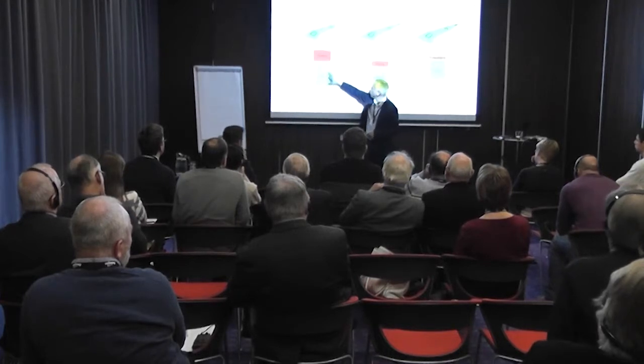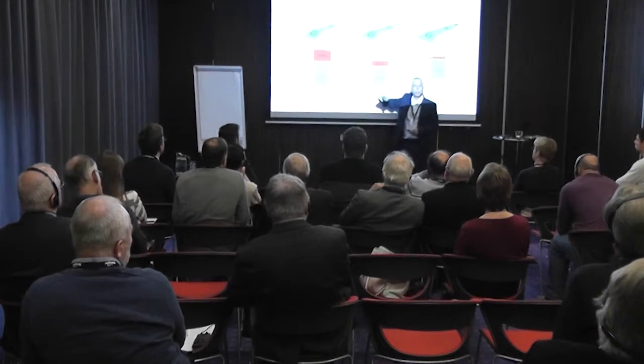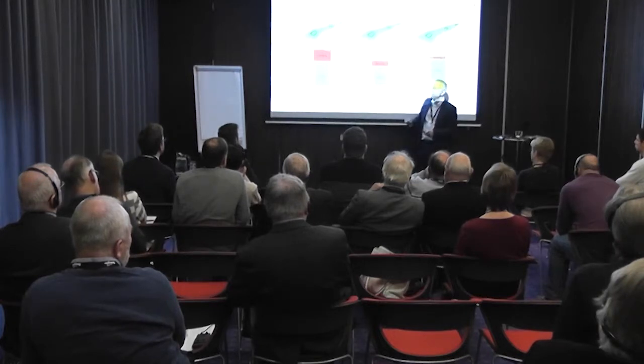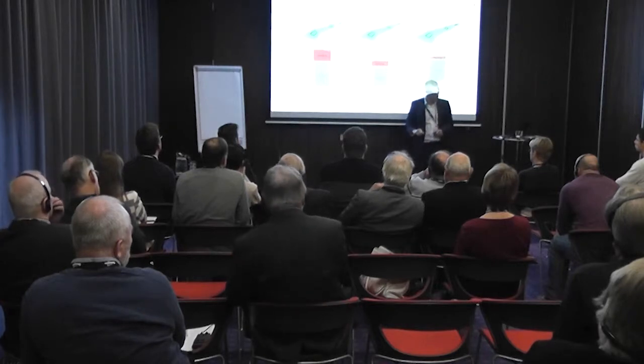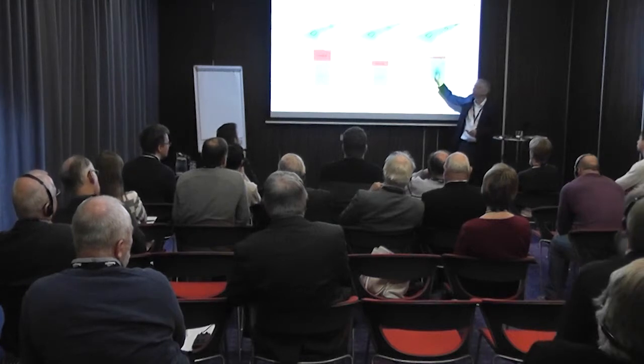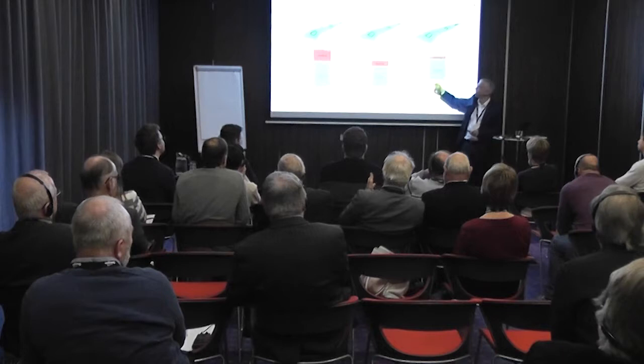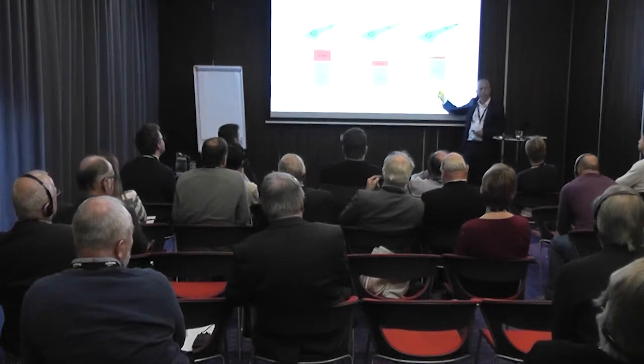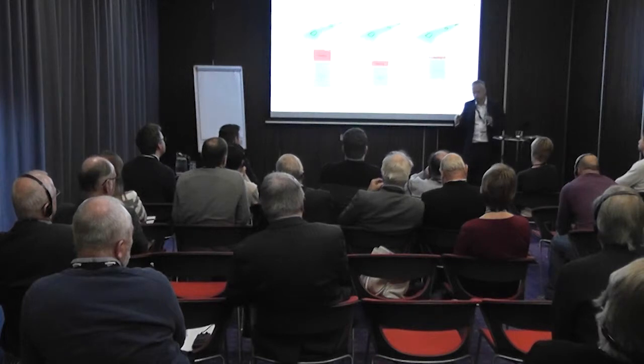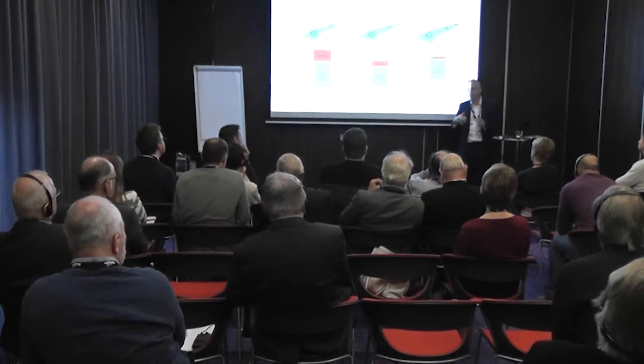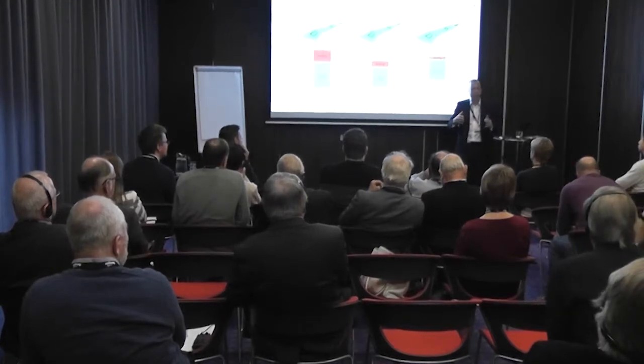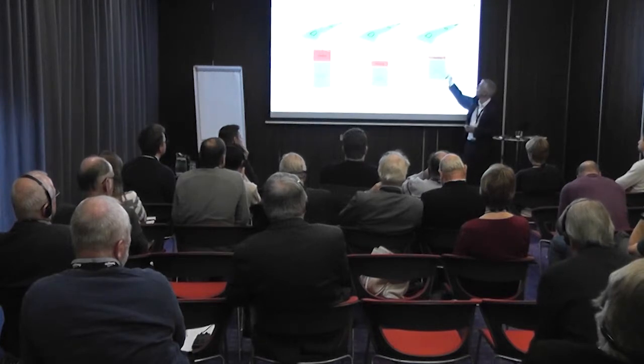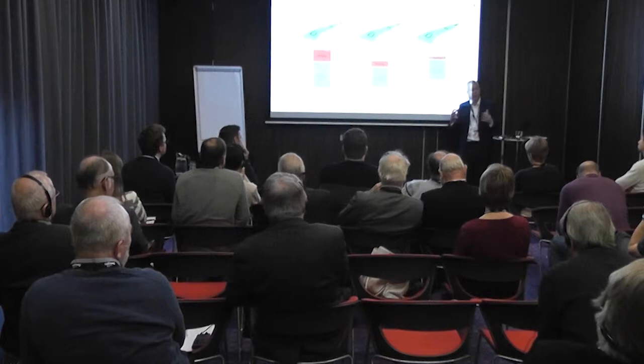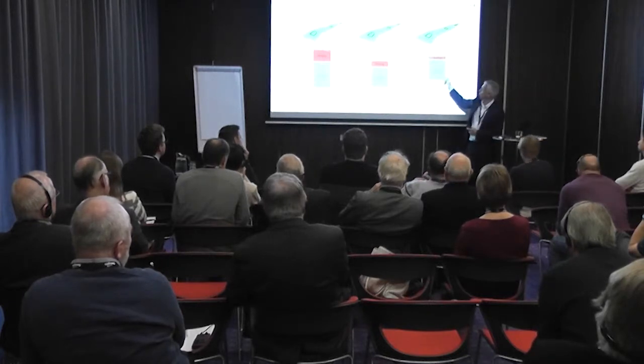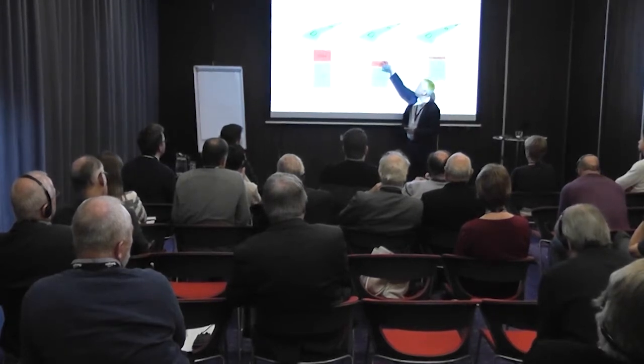With 100% glass we had lighting, cooling and heating energy to consider. As you move to 50% glass, you got quite a lot of reduction, particularly in cooling and heating. But if you move even further to just 30% glass, that trend started reversing, and the cooling profile started going up again. This was happening because of internal heat gains generated by computers and occupants, which is energy you need to get out of the building. So if you make the facade too solid, that heat gets trapped inside. We found the optimum was somewhere around 50%.